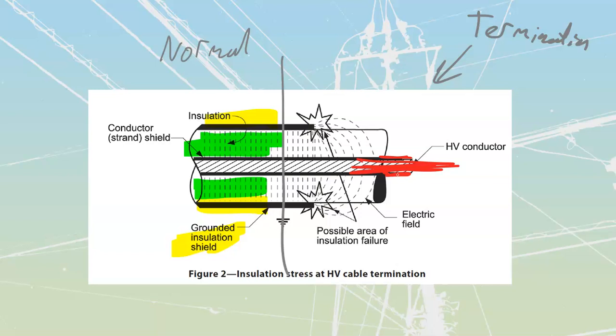We see this conductor going through the inside, and on the outside we have the insulation shield. Because that insulation shield stops over there, when it comes to my termination I'm going to have to do a bunch of stripping of my cable.